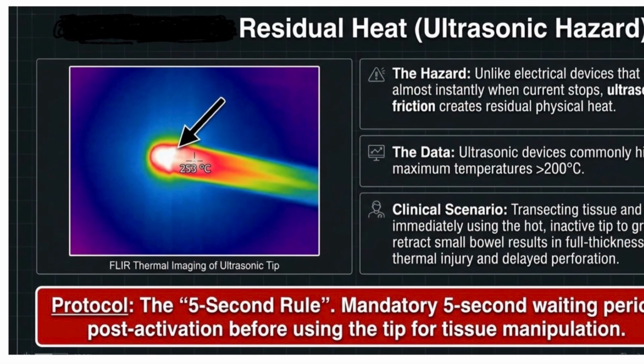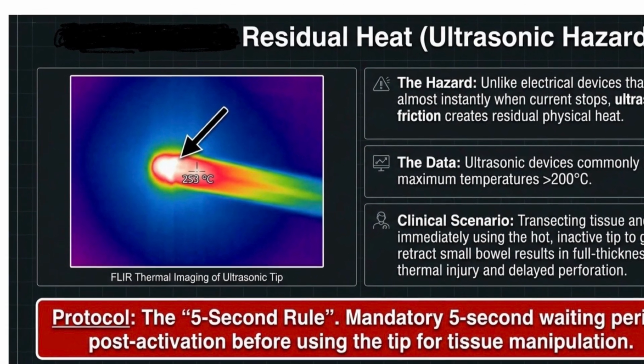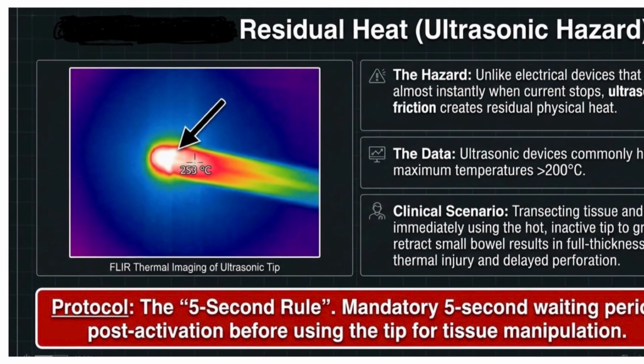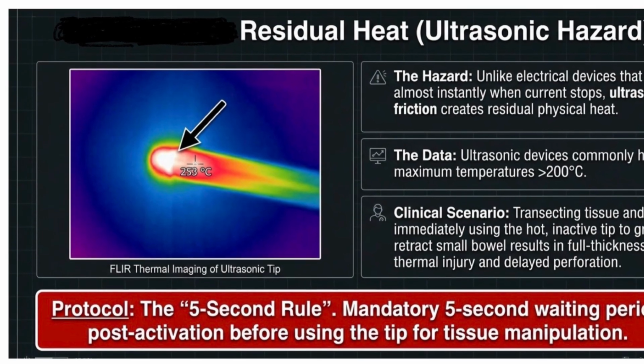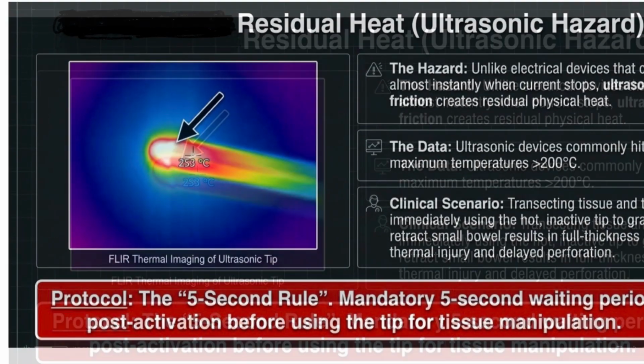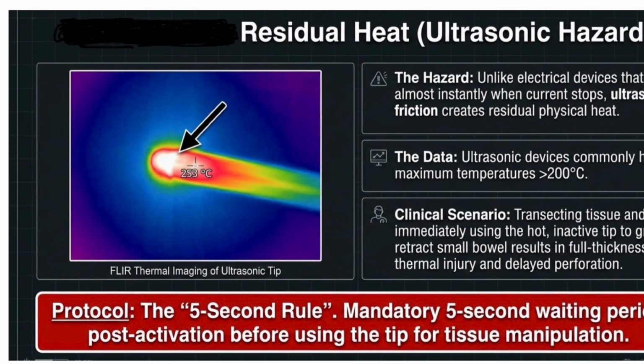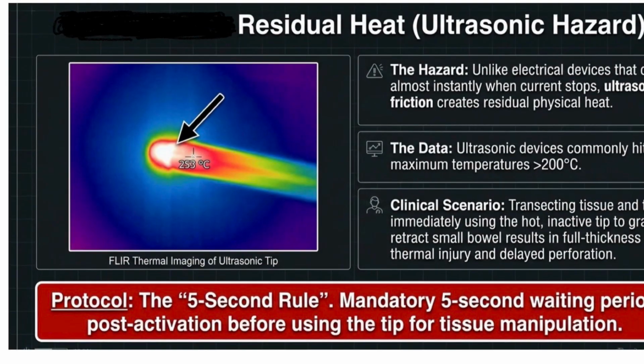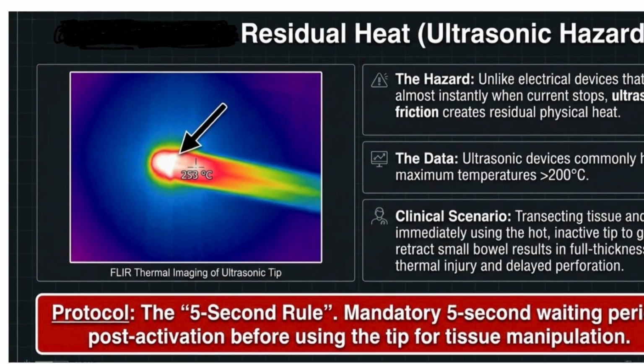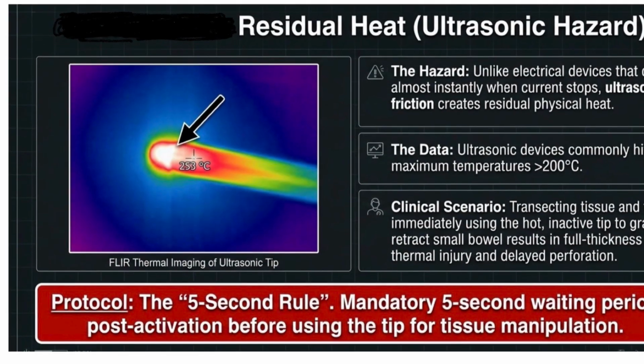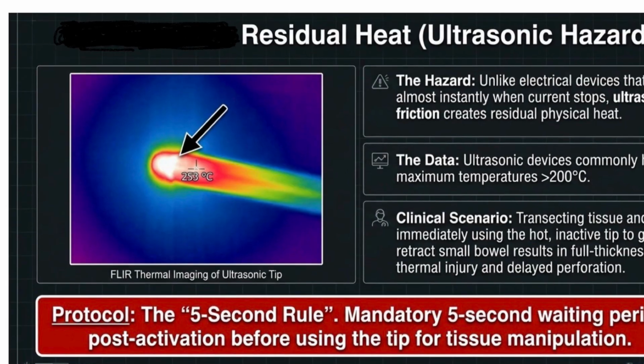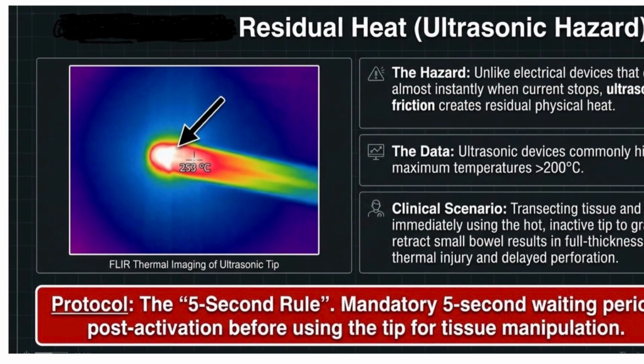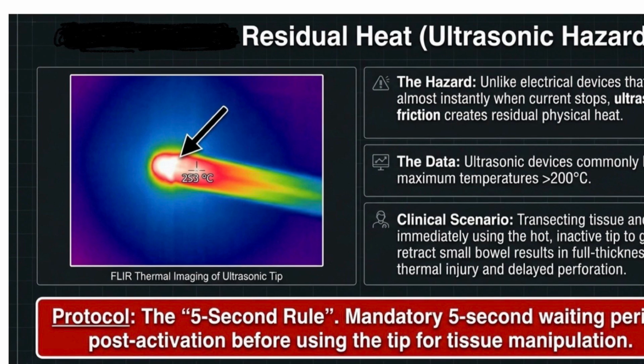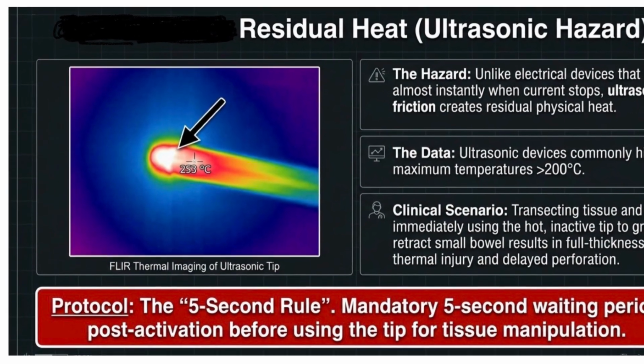The residual heat, we have already discussed in the ultrasonics. Unlike electrical devices that cool almost instantly when current stops, ultrasonic friction creates residual physical heat. Ultrasonic devices commonly hit a maximum temperature of more than 200 degrees centigrade. So transecting the tissue and then immediately using the hot inactive tip to grasp and retract small bowel results in full thickness thermal injury and delayed perforation. The protocol to be followed: the 5-second rule, a mandatory 5-second waiting period post activation before using the tip for tissue manipulation should be followed.